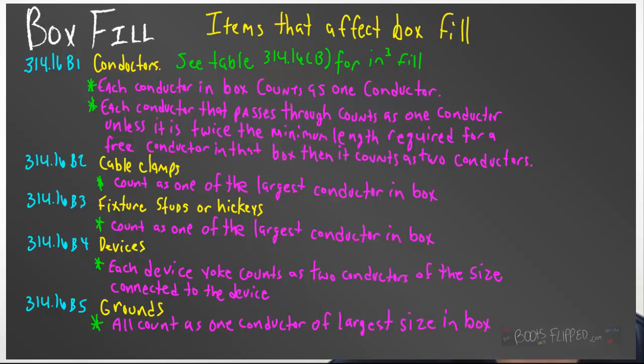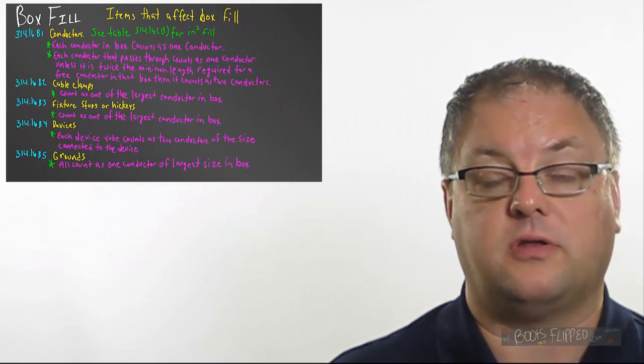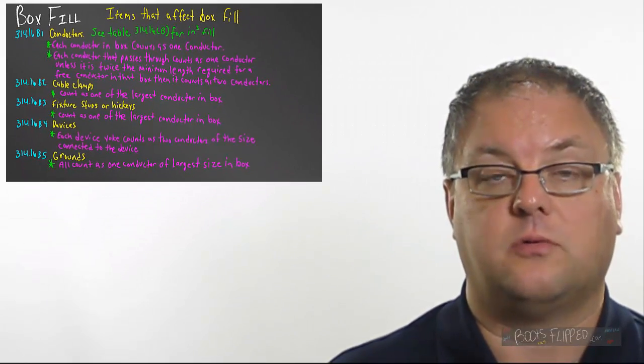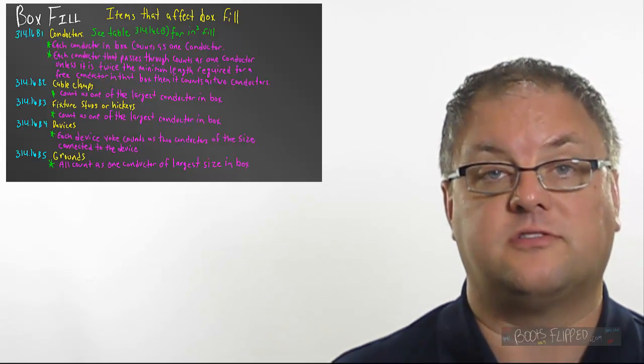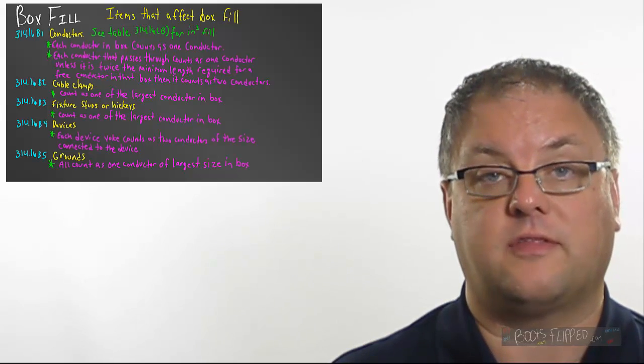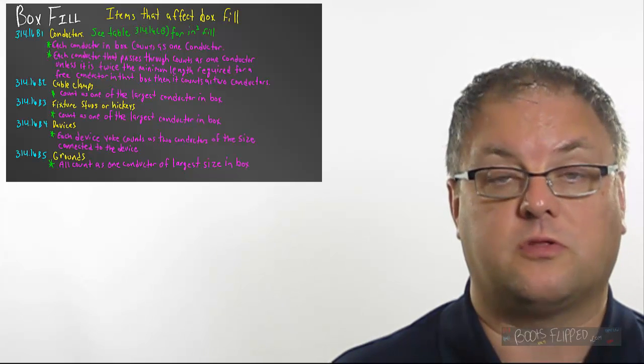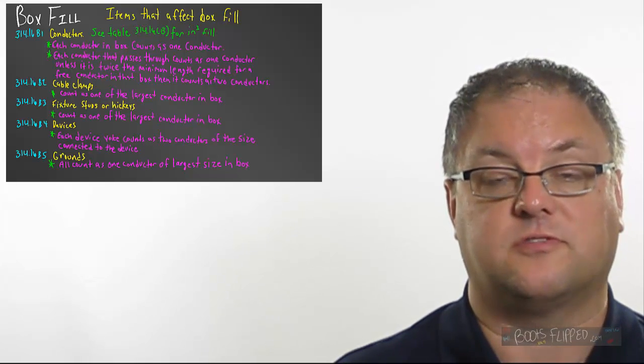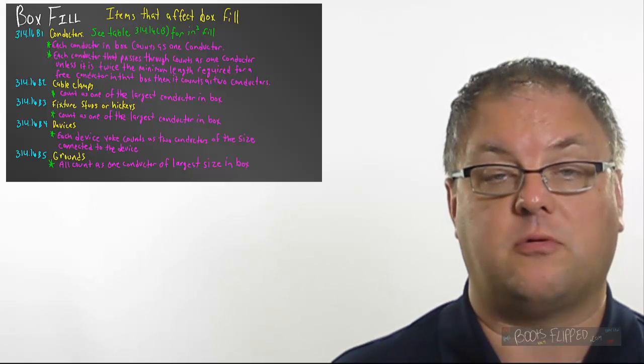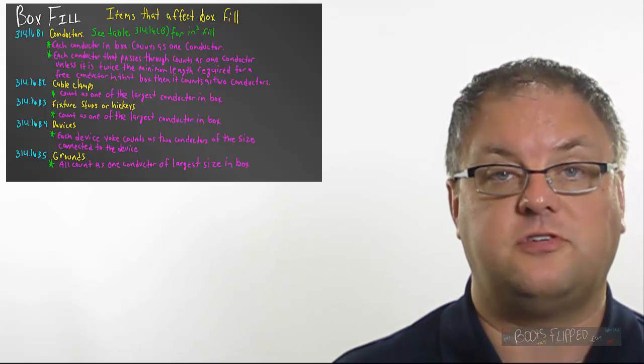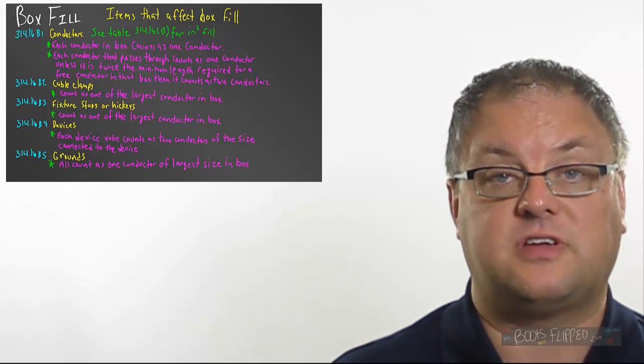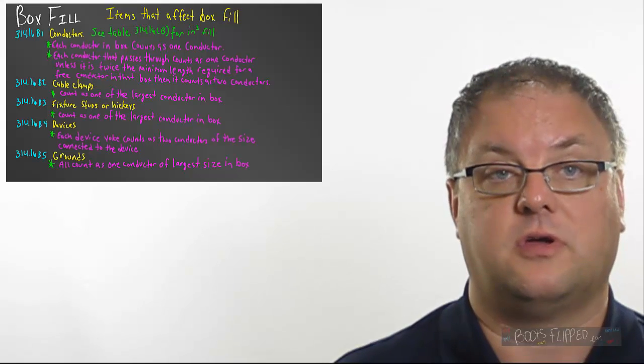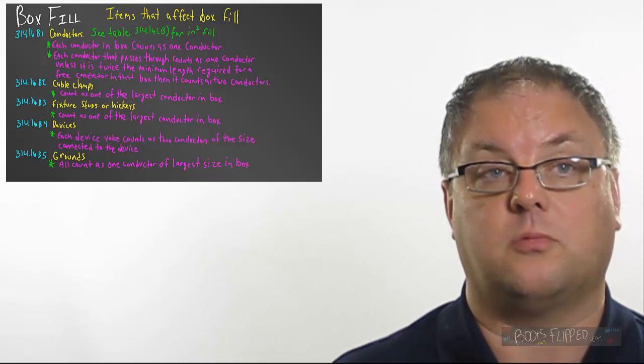This code article also tells us that every conductor counts as one conductor, whether it comes out of the box or it passes through the box. Now, if we do loop our conductors through the box, which you'll see in a lot of commercial applications, if that conductor is twice as long as the conductor length that's required to meet code, which we learned last time was six inches of conductor from where it enters the box, so that would be six inches times two, we would have 12 inches of conductor. If that is the case, then you have to count it as two conductors.